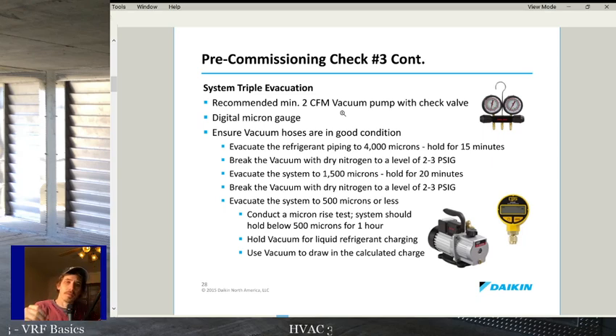Getting full flow, they're popular at this point, but the Schrader removal tools that you can take the Schraders out while you vacuum save a ton of time when you're evacuating. And if you've got like that 7 or 8 CFM vacuum pump, you might actually be able to use some of that capacity, whereas if you're only pulling through a Schrader valve, you're probably only pulling at about a half a CFM anyway. You need a good digital micron gauge that you trust the readings on, which reminds me, I've got to clean my gauge tonight because it's a little contaminated. It's still okay, but not great. Got to clean my gauge.